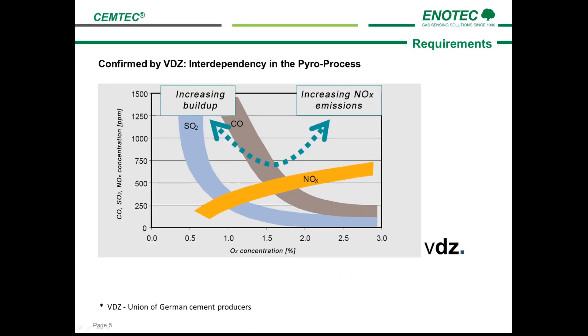Let's take a look at this graph from the Union of German Cement Producers, the VDZ, which confirms the interdependency of O2, CO, and NOx in the pyro process. We see the O2 concentration in percentage here, and the concentration of CO, SO2, and NOx in ppm here. The excess O2 sweet spot from the main burner will be around this area, between one and two percent. As you can see, this concentration of excess O2 influences the values of CO and NOx and contributes to build-up in regard to SO2.